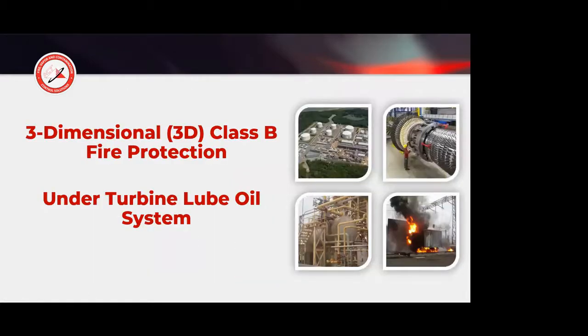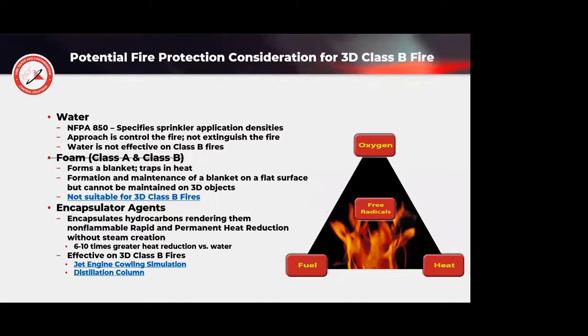Three-dimensional Class B fire protection has multiple applications. We're just going to highlight a couple. The under turbine lube oil spray system. Again, we look here and we go, okay, these are our considerations. We can use water. When we look at the NFPA standards, it specifies application densities.